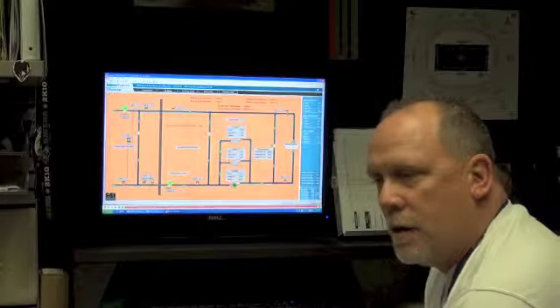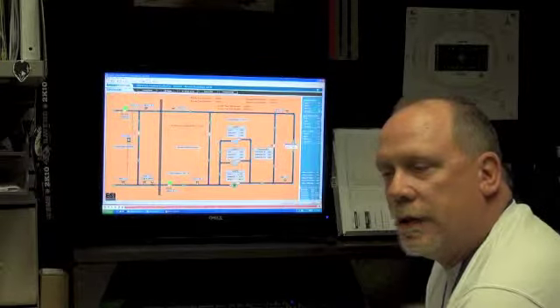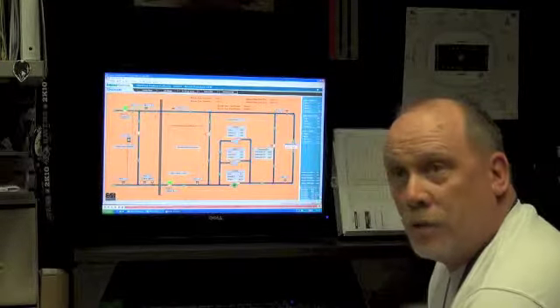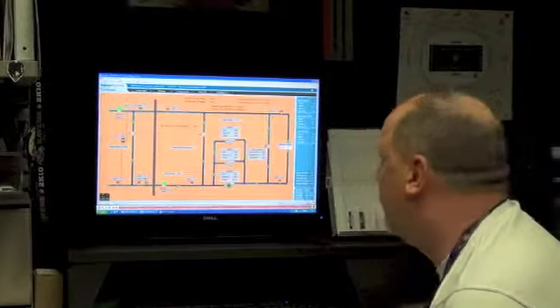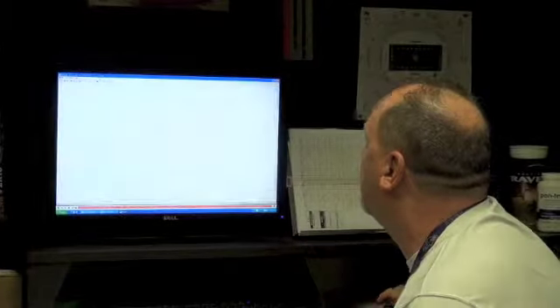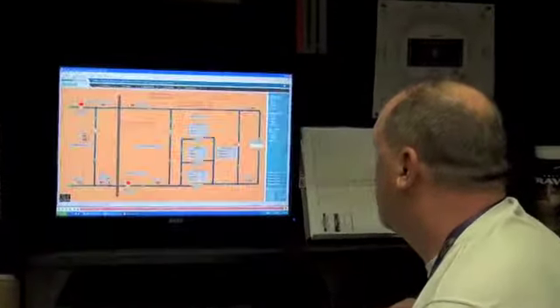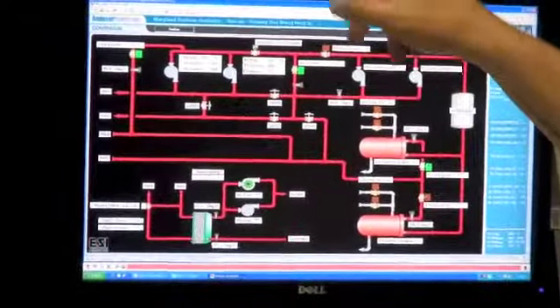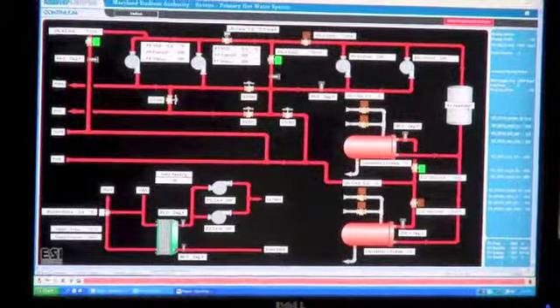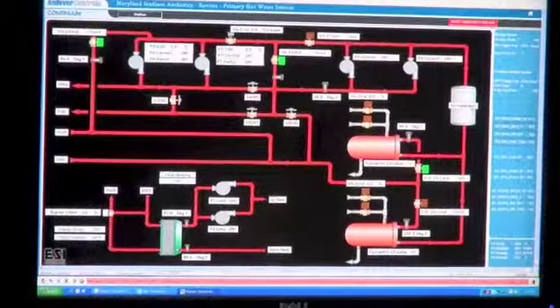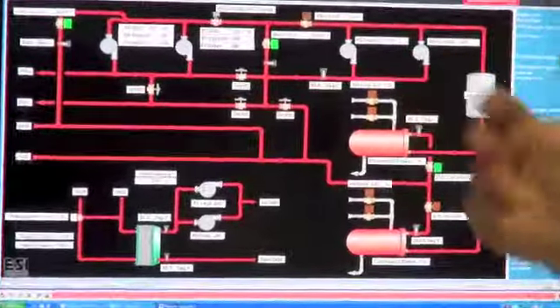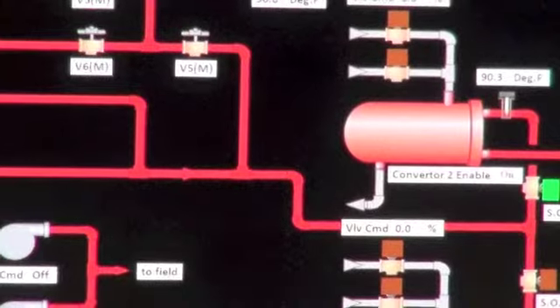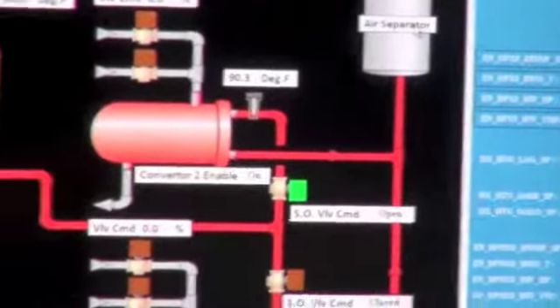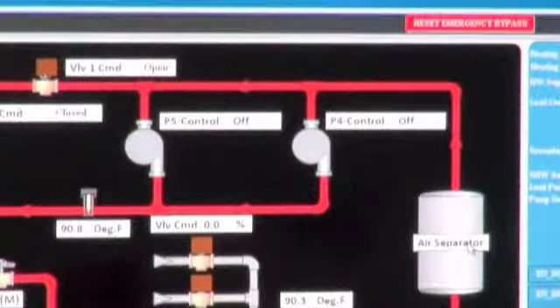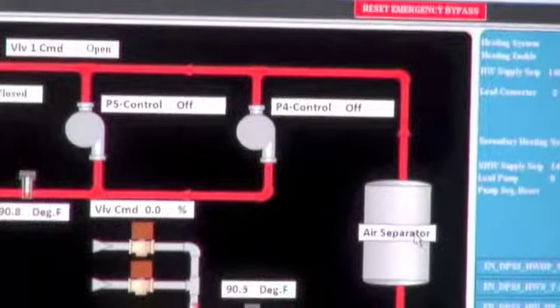As far as heating, we're steam heated. We get our steam from a supplier in Baltimore. They supply steam. We have a steam plant, our hot water plant, which monitors. All we have here, we have 2 converters down in the steam room. We have 4 pumps that supply the building. So we mainly maintain, we'll see what kind of temperature we have to the building, make sure we have enough steam. If it's not, we get on a horn and say, hey, we need more steam, our building's not keeping up, or so forth. We also have a field heating system, which we do heat the field.